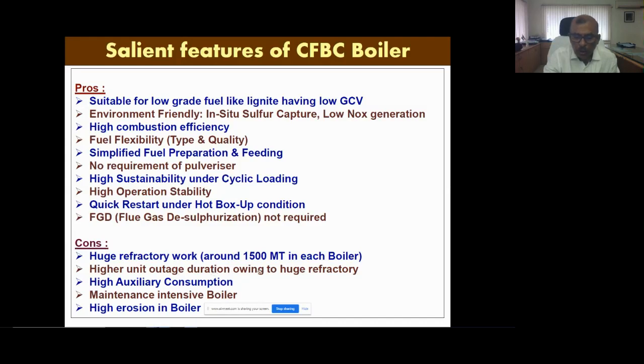Whenever there is a tube leakage or forced outage, this causes a much higher unit outage. Then, in this boiler there are a lot of auxiliaries, like the many blowers for fluidization and the lime milling plants. It causes higher auxiliary consumption, in the range of 11 to 12%. It is also a maintenance intensive boiler, because with a lot of heating surface area there is an issue of high access and approach. And since the bed material is ash, when it slides down or moves in the boiler, it causes heavy erosion in the combustor and other areas.